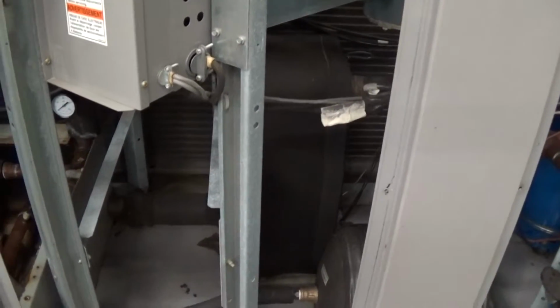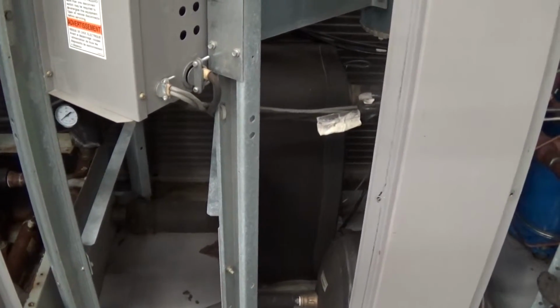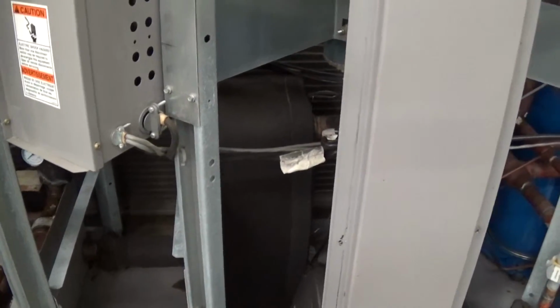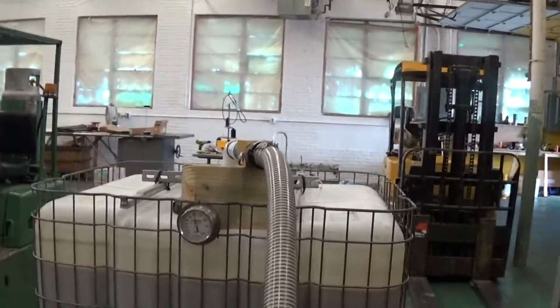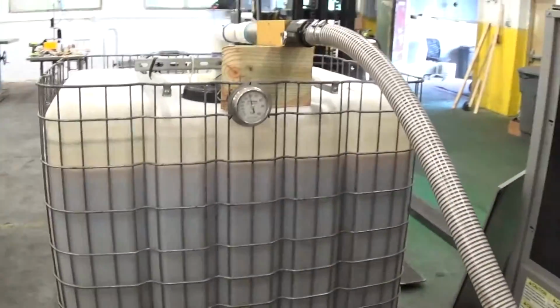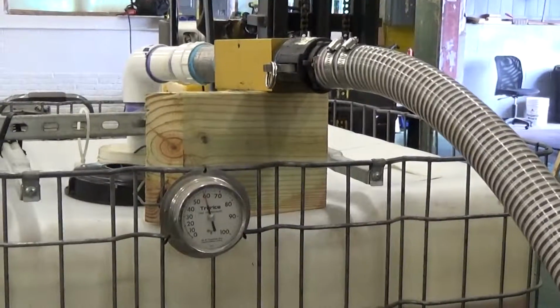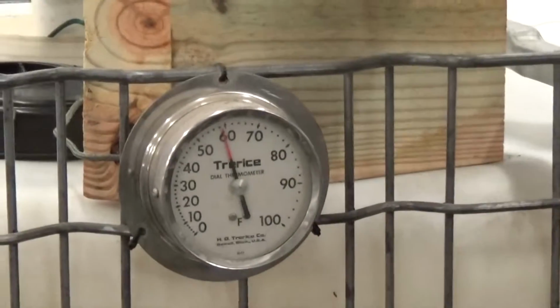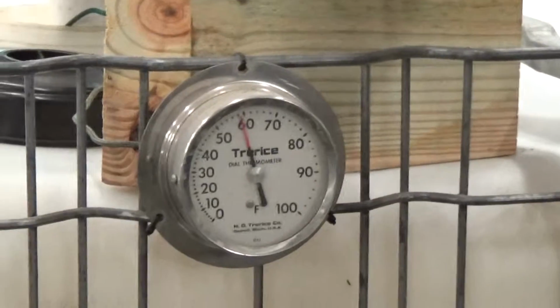So it's coming in, and we're pushing the fluid directly into the heat exchanger. That takes care of all the pressure and GPM requirements internally for the chiller, and then that chilled fluid will go out to your process and then back to what will be the equivalent of your tank in your shop. So we're going to put the covers back on and turn this on. Our tank right now is at about 60. We're going to do our test and chill down to 25 Fahrenheit.